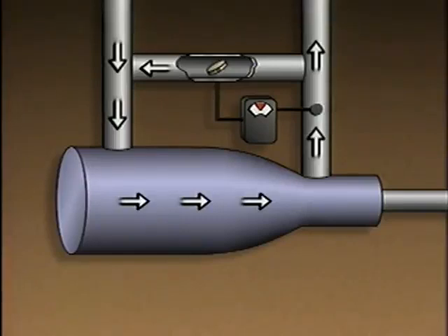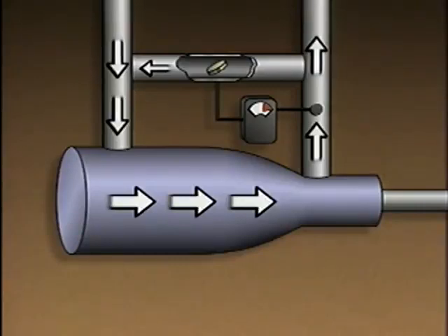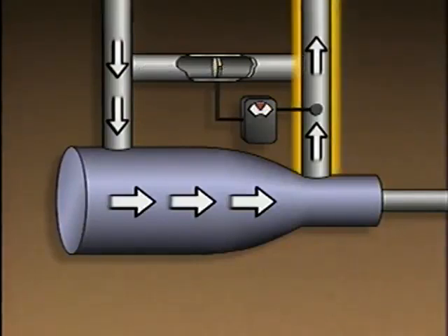When demand increases, gas flow through the compressor also increases. When the gas flow is high enough to prevent surge, the flow controller closes the recirculation valve. The gas flow from the compressor is then directed only through the discharge piping. In this topic, we looked at the functions of instrumentation and control devices commonly used with centrifugal and axial compressors. We also saw how surge control can be achieved.